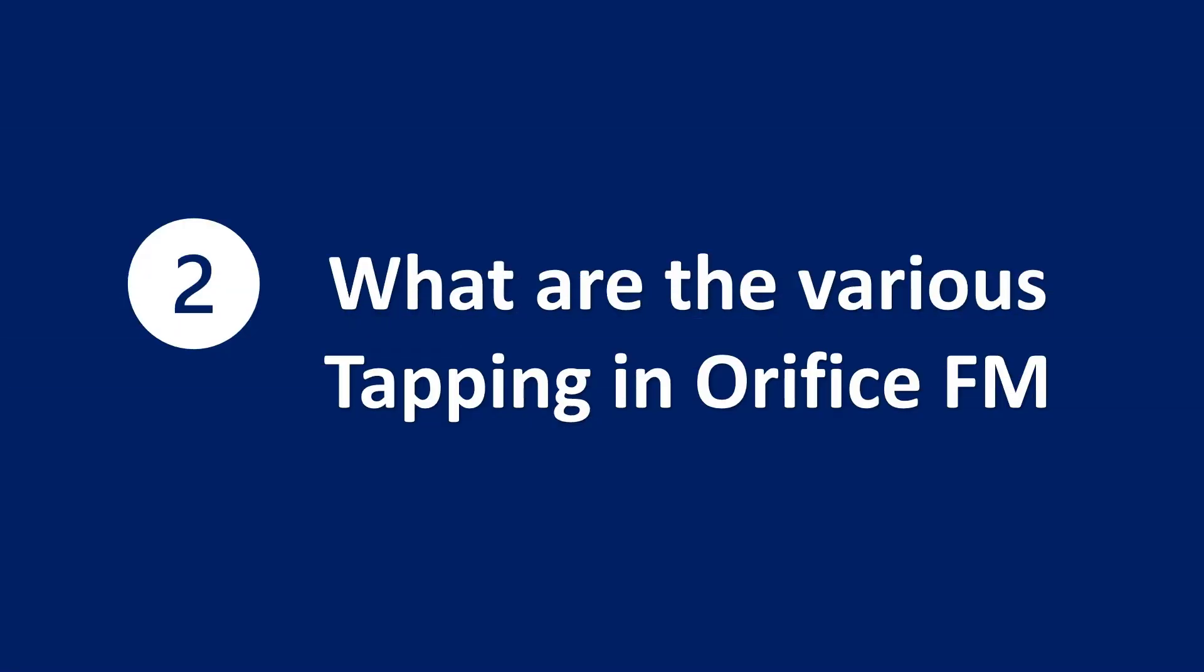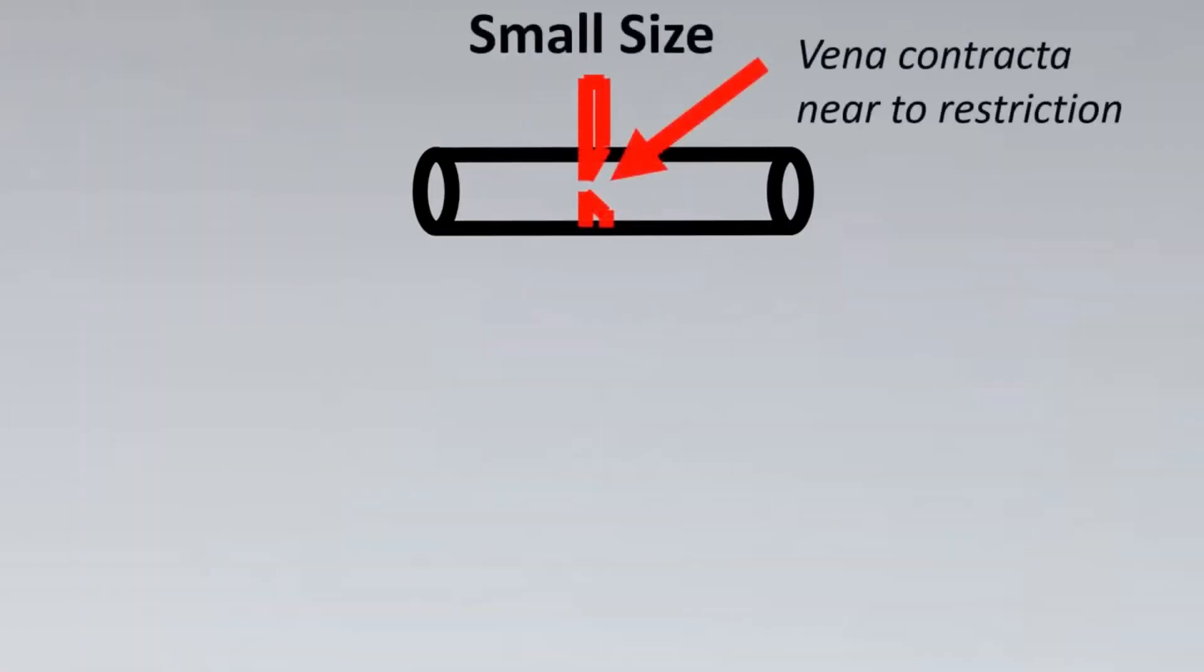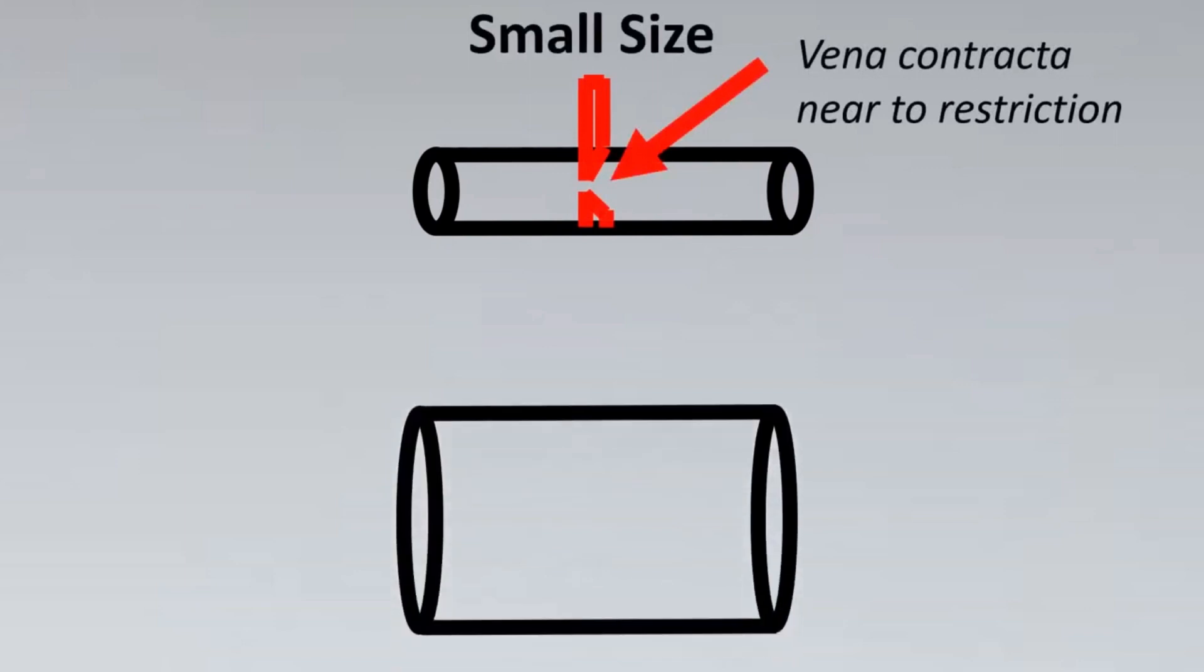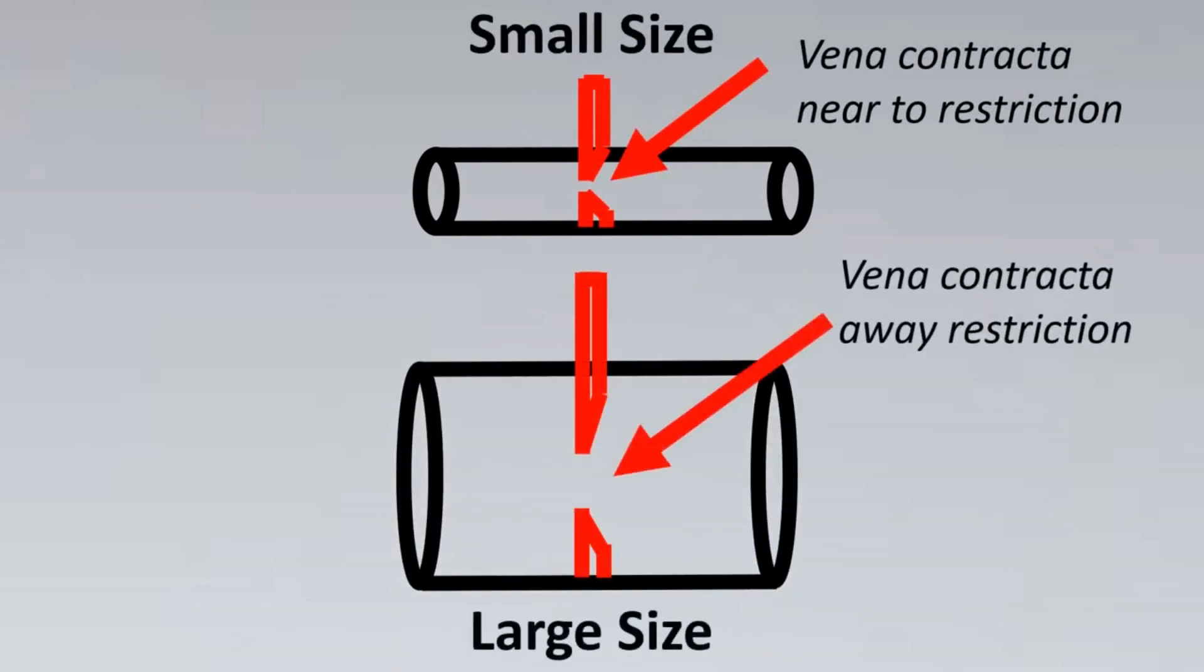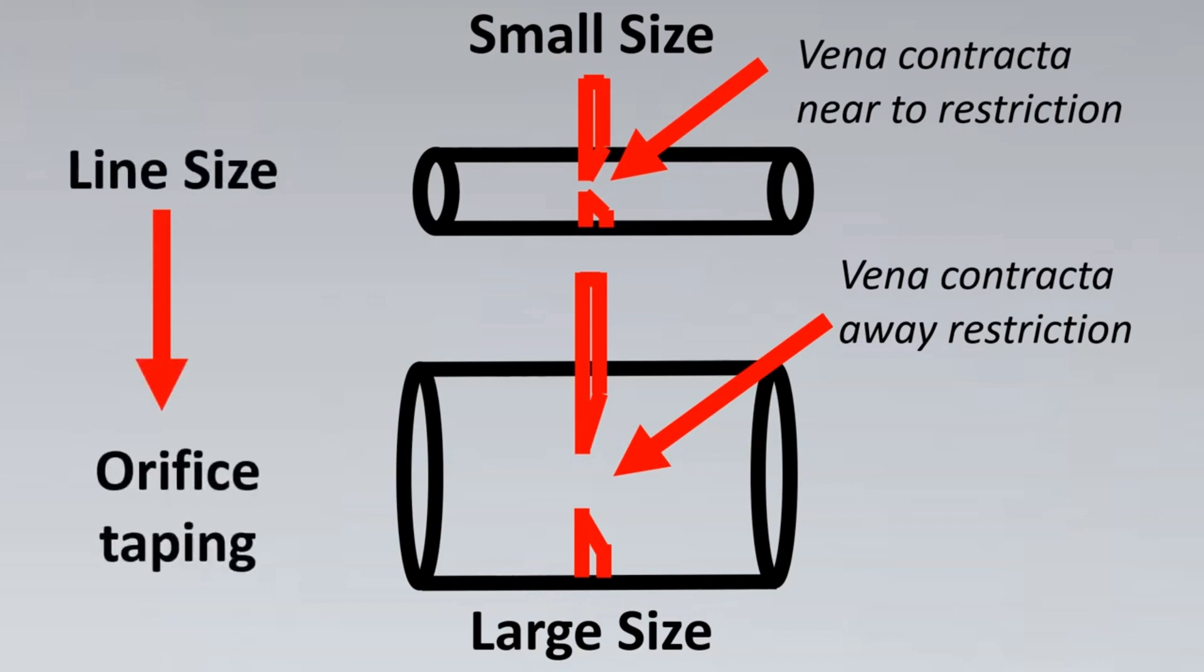The second most asked question is what are the various types of tapping available in orifice flow meters? This concept depends upon line size. For smaller line sizes, the Vena contracta is near to the restriction. However, for larger line sizes, the Vena contracta would be away from the restriction. Does that have any issue on our tapping selection? Absolutely, it has an effect on the selection. The line size basically helps us decide which orifice tapping to take. If the Vena contracta is nearer to the restriction, the tappings would also be taken from near to the orifice. And the farther the Vena contracta is from the restriction, the tappings are taken from that distance or as much approximation as possible from that distance to get the best DP that is available.